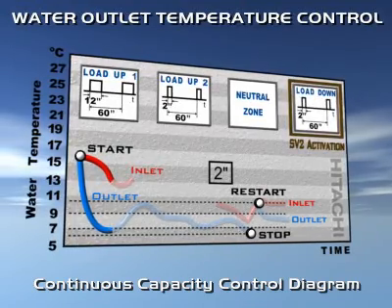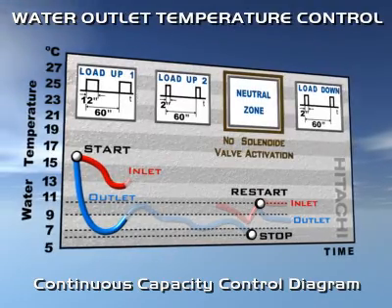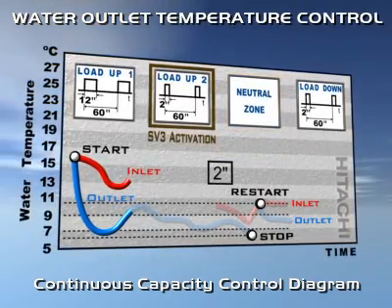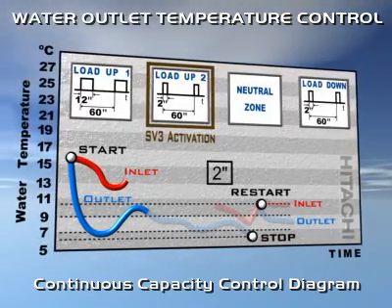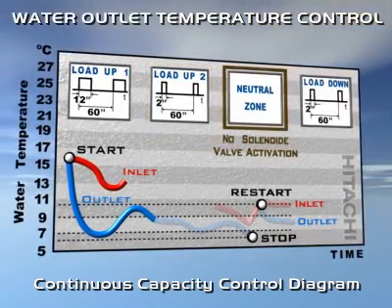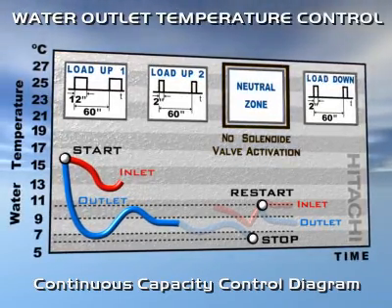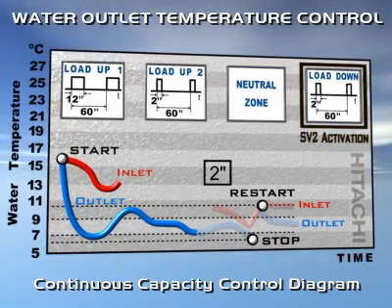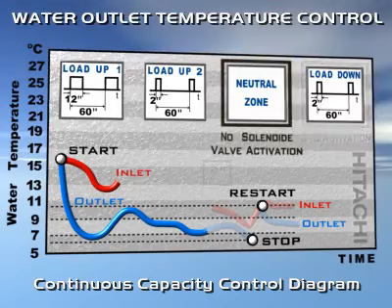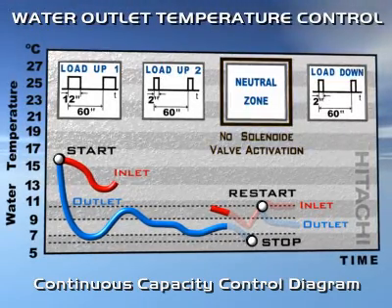Given a load and having selected a cold water outlet temperature, the electronic system compares the value measured by thermistors with the desired value. Depending on the measured value and at one-minute intervals, a control signal is generated that varies the position of the sliding valve either to increase or to decrease the capacity as required. The control signal is sent to the solenoid valves located in the compressor, and those valves command the sliding valve's movements.